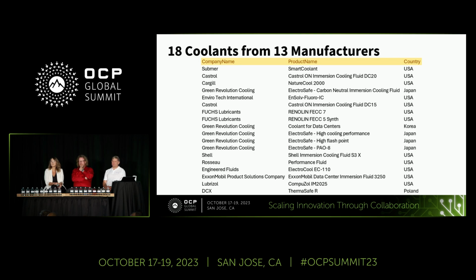It's always going to be a balancing act between what I'd like as a heat exchanger manufacturer versus what we need in terms of the fluid properties for conductivity and things like that. We are doing some testing on different things. Material testing from a heat transfer point of view - predominantly using copper brazed heat exchangers, which will be stainless steel and copper. But there are lots of other possibilities when you get onto larger systems that might involve gasket materials, so rubbers and elastomers used within the heat exchanger. We're doing testing around that at the moment to see, does it have to be a Viton-based gasket? Can we look at more commonly available gaskets such as nitriles and see how they react in terms of swelling and degradation, to make it more viable and more readily available into the market.